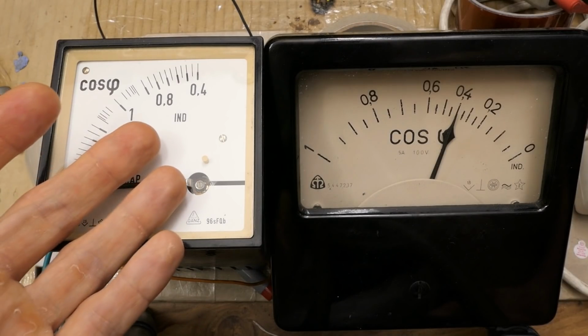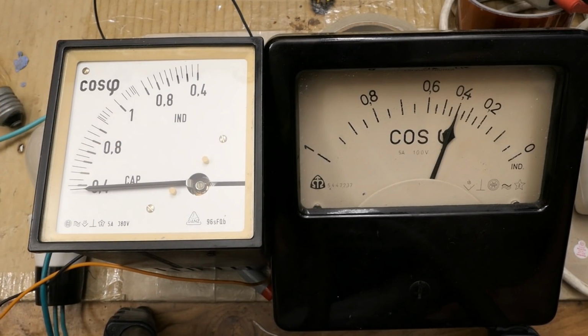So the system in power factor meters is completely different than the system in voltmeters, current meters or wattmeters. In a voltmeter, current meter or wattmeter, there is a magnetic torque generated and this magnetic torque goes against the spring trying to bring it back. So it basically measures the magnetic torque. The more magnetic torque, the more deflection.